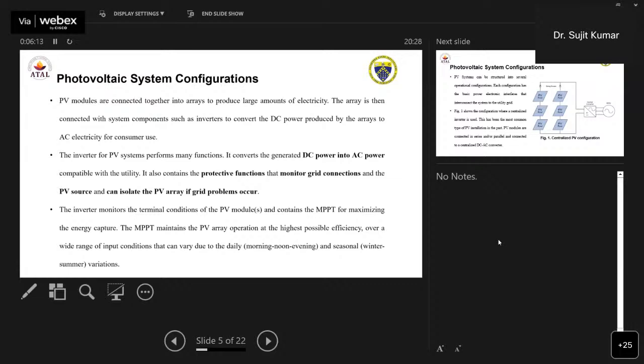So the inverter also monitors the terminal condition of the PV module and contains the MPPT for maximizing the energy capture. This MPPT maintains the PV operation at the highest possible efficiency over wide input conditions, because it is going to vary from morning to noon, noon to evening, and seasonally, like what the variation is in the winter season and in the summer season, so that it optimizes at that single point only. We are going to have the particular maximum power point. From there, we have to take care of which parameters we get it from and how the parameters are going to be optimized. Okay.